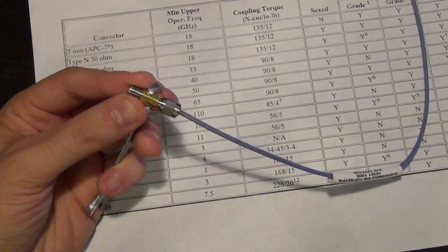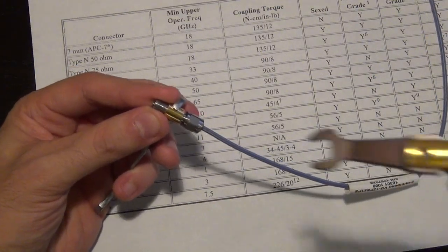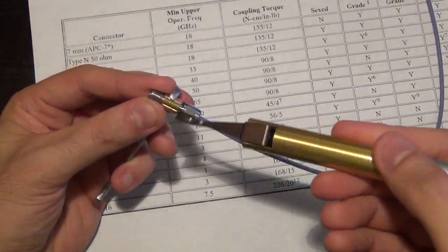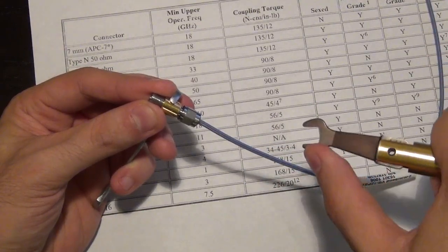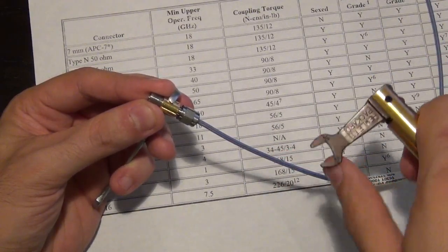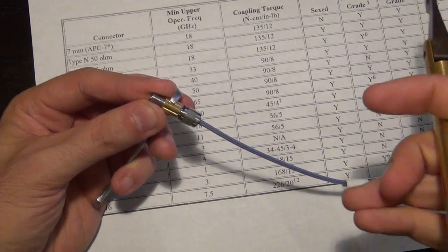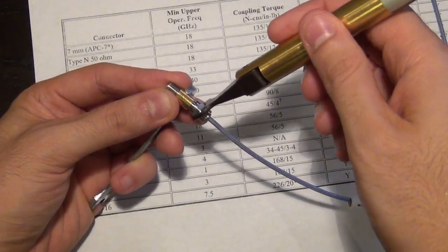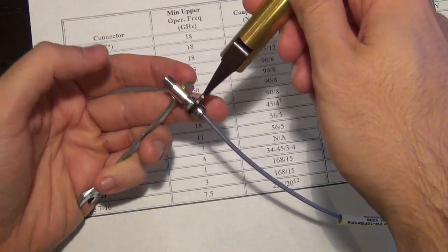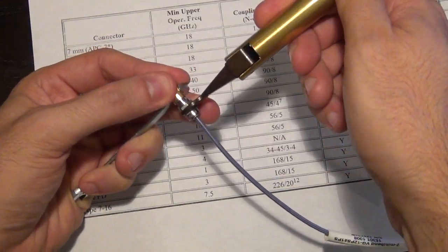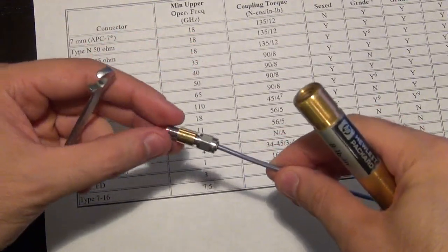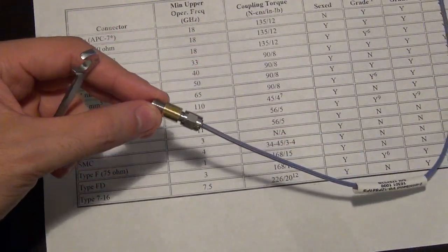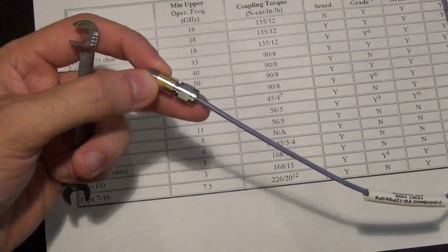And now I move on to the torque wrench. Here's an example of a torque wrench. This is a Hewlett-Packard one, and these torque wrenches are tuned to a particular torque. You can see that the tip will actually bend as soon as it reaches the correct torque. So I will now place this, and I'm holding the other wrench with my hand. Now we'll continue until the wrench is bent. And now this connector is tightened to the proper specification. You should never over tighten it, and you should never have it too loose.